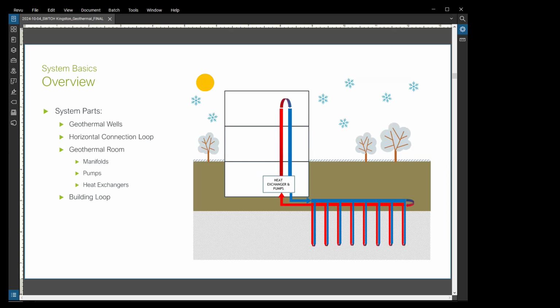So the reason why there are heat exchangers in the basement of the building, where we're going from the ground loop to the building loop, is that in the ground loop we typically put something like a glycol into the loop to make sure that the fluid doesn't freeze. The ground temperature, when you get deep enough, basically equilibrates. So it's not such a concern about freezing at depths, but in that first few meters, where it's more susceptible to the exterior air temperature, there could be some risk of freezing. So we want to make sure that we don't have any slush or anything that would impact the performance of the fluid. The glycol is typically not a fluid that we want to have running through the building because the heat pumps in the units don't use glycol. There are units that do, which we'll talk about a little later, but essentially that's why there is a heat exchanger down at the bottom of the building.